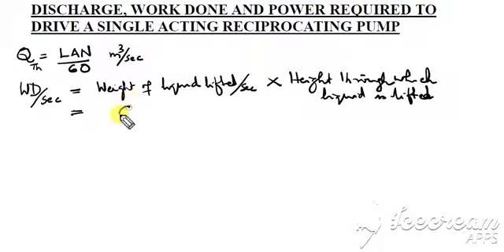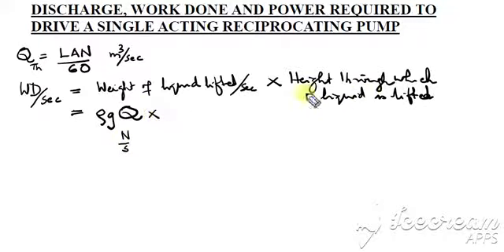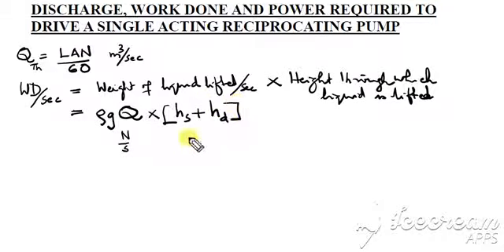The weight of liquid lifted is essentially the weight flow rate. You have the discharge Q; if you multiply this by rho you get mass flow rate, and if you multiply by rho times g you get weight flow rate. So rho times Q is mass flow rate in kilograms per second, and once you multiply by g it becomes weight flow rate with units of newtons per second. Multiplying by the total height — suction head plus delivery head, the total static head — in meters gives newton-meters per second, that is joules per second, that is watts.